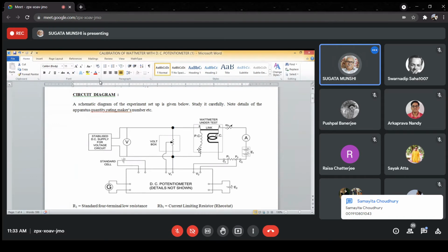But will 20 watts actually be consumed from the supplies? It won't be. This voltage E1 from which the current coil is supplied, say its voltage is around 2 volts. Consider the extreme case. The wattmeter is reading 100 watts. If you had used a physical load as indicated earlier for calibration, then when the wattmeter reads 100 watts, it means that the physical load actually consumes 100 watts. But here what will happen? Voltage across the potential coil circuit is around 100 volts. You have to inject a current of 1 ampere through this current coil. So 1 ampere into 100 volts will give you 100 watts. The wattmeter will indicate 100 watts.